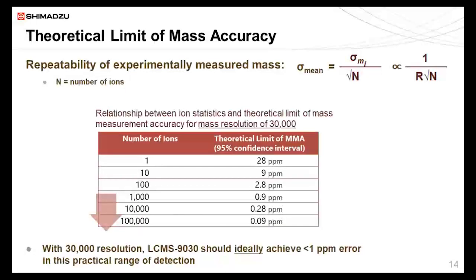And in this table, in the center, this shows the relationship between ion statistics and theoretical limit of mass measurement accuracy for mass resolution of 30,000. So for an instrument of 30,000 resolution, if you sampled one ion, it's 28 ppm. But if you're measuring 1,000 ions, the best performance we would expect to see is 0.9 ppm, 95% confidence interval. And if you've measured 10,000 ions, it's 0.28 ppm. So even with an instrument of 30,000 resolution, we should ideally achieve better than 1 ppm error in this practical range of detection, because normally you're not just measuring 1 or 10 ions, but you're playing around with thousands of ions.